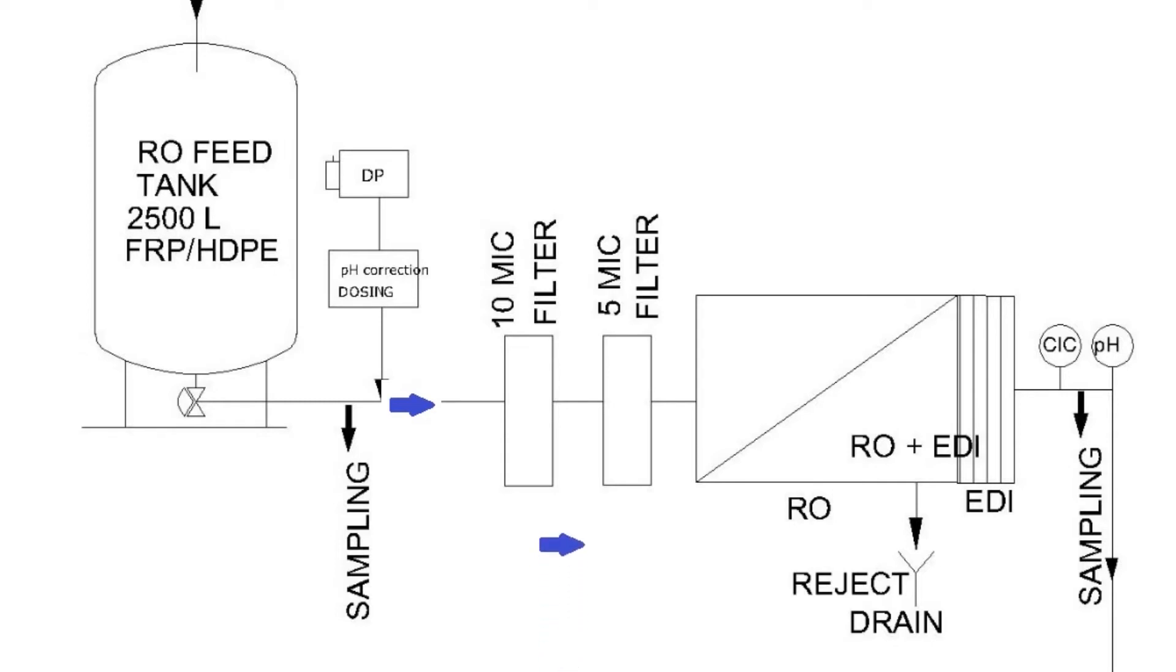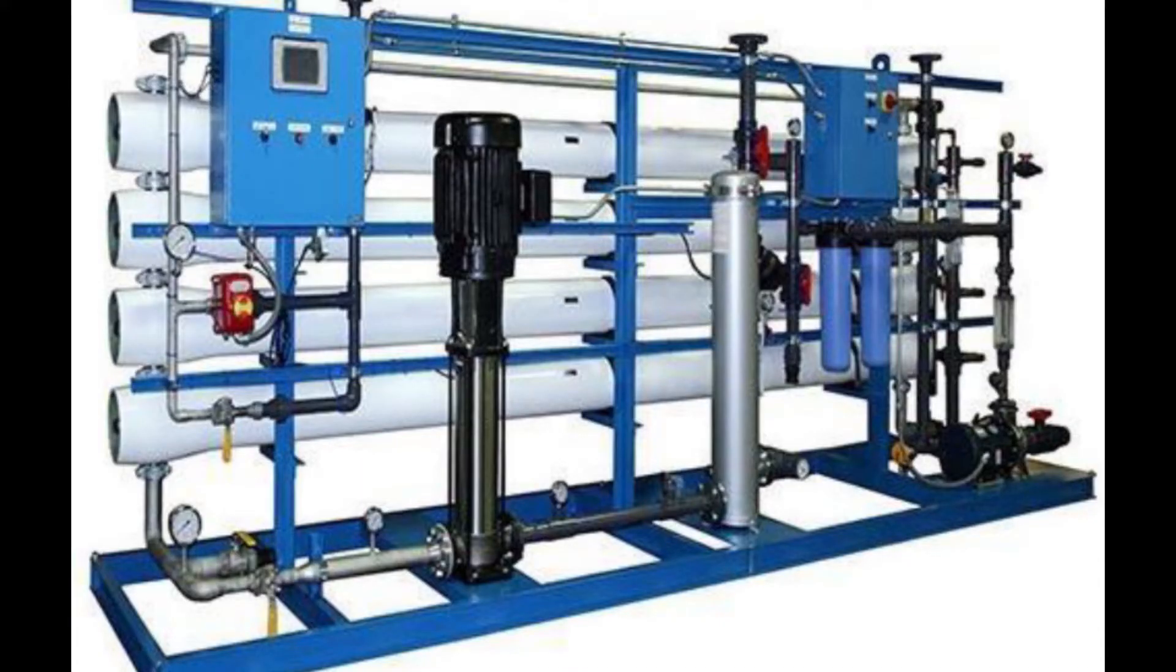Potable water is fed into the reverse osmosis system to generate purified water of pharmaceutical grade. Reverse osmosis, commonly referred to as RO, is a process where water is demineralized by flowing under pressure through a semi-permeable membrane. A high pressure pump is used to increase the pressure on the feed water side of the RO and force the water to flow across the semi-permeable membrane, leaving most part - approximately 95 to 99 percent - of the dissolved salt behind the stream.